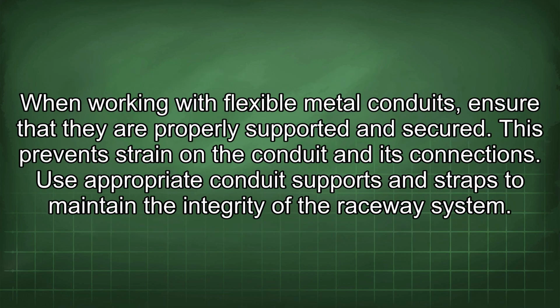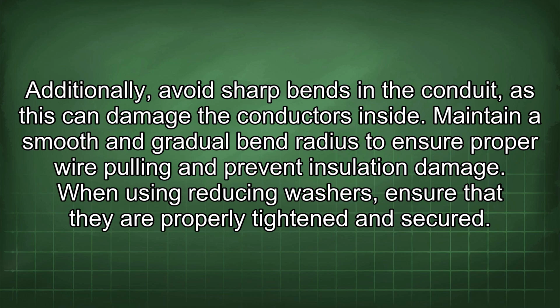When working with flexible metal conduits, ensure that they are properly supported and secured. This prevents strain on the conduit and its connections. Use appropriate conduit supports and straps to maintain the integrity of the raceway system. Additionally, avoid sharp bends in the conduit, as this can damage the conductors inside. Maintain a smooth and gradual bend radius to ensure proper wire pulling and prevent insulation damage.